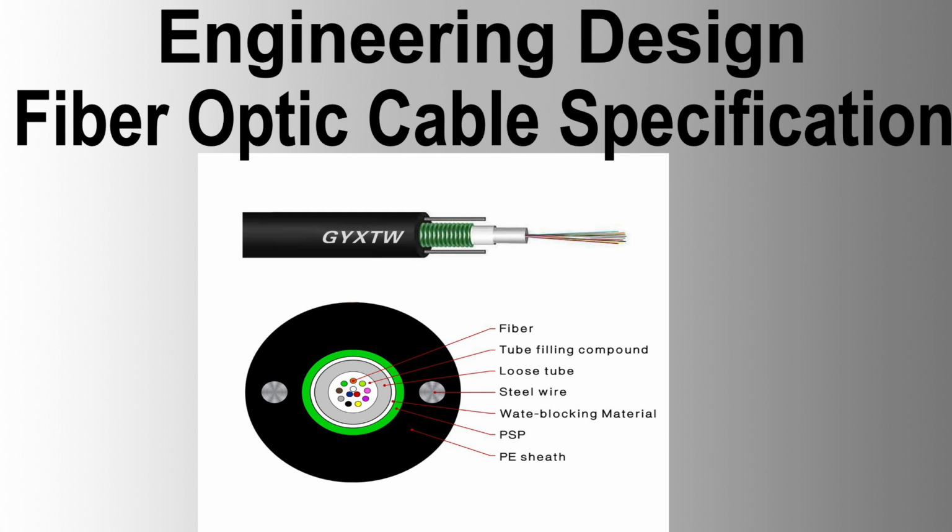Stress strain, tensile load. The test must be carried out in accordance with IEC 60794-1-E1 to determine the tensile characteristics of the cable under load and to verify the fiber strain margin within the cable. The maximum change in the optical attenuation at the cable's rated maximum working tension shall be no greater than 0.1 dB at 1550 nanometers for FOC installed in HDPE conduit.